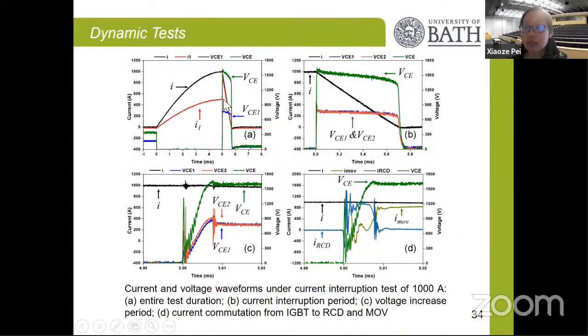So we investigate the current, and we can say that in a dynamic change with our design, we are able to achieve very balanced current in those two parallel branches. And then when the current rises to 1,000 amps, we start to interrupt the current. When the current is interrupted, we observe the voltage drop across the series connected IGBTs. So we can say the voltage drop is very balanced across those two elements, and this is the total voltage drop. With our design, we are able to achieve a very balanced current during the steady state and the dynamic state. And at the interruption stage, we are able to have a very balanced voltage level across the series connection. This is very important because it means we are able to use series connection and parallel connection to increase the current level and the voltage level of the DC circuit breaker.